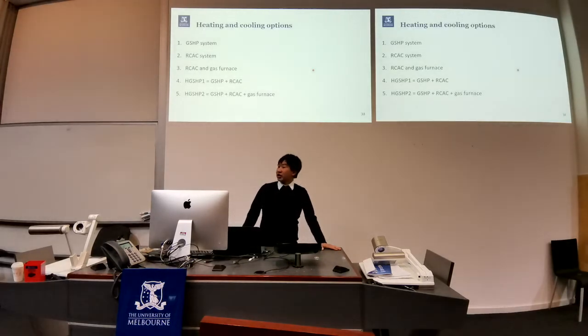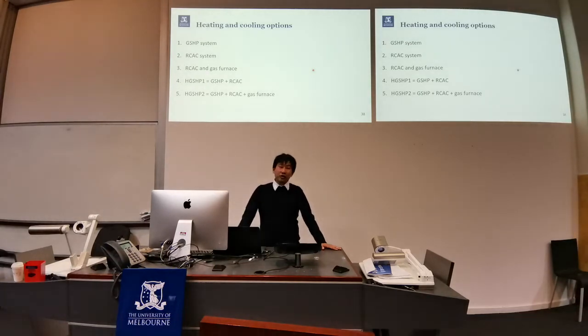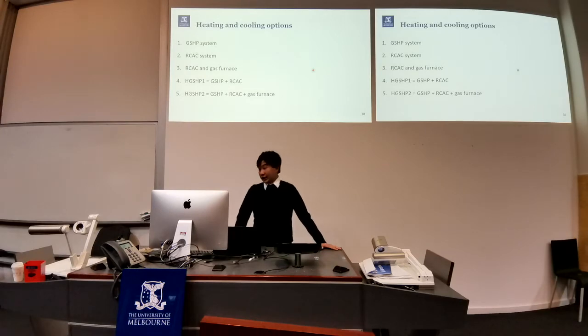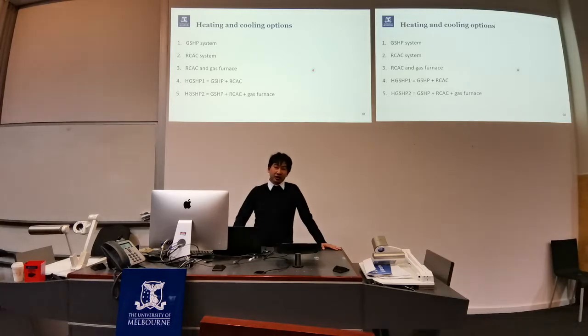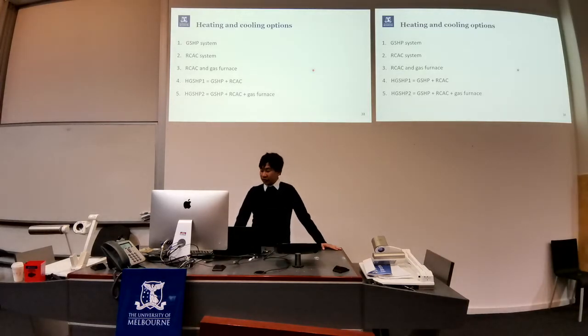Based on this energy requirement, five heating and cooling systems are considered in this study. The first is a ground source heat pump system, and then we have two different conventional systems. The first is reverse cycle air conditioning that is used for both heating and cooling. And then we have the same aircon used for cooling only, but the heating is provided by gas. And then we have two hybrid systems. A hybrid system is a combination of a ground source heat pump system, which is designed to provide the base load, and this is supported by a conventional system during the hottest and coldest days of the year.